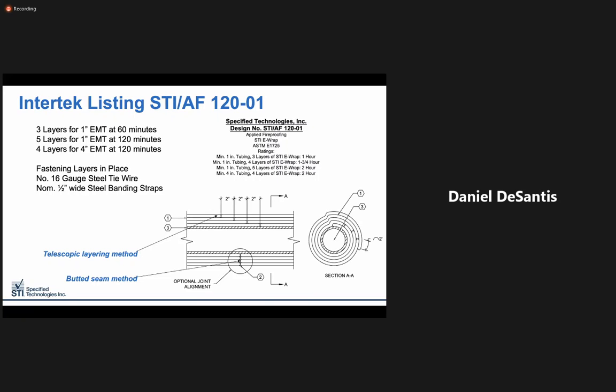When a butted seam method is used, a bead of LCI intumescent sealant is required on the outermost seam, where no additional sealant is required for the telescopic method. Either installation is completely acceptable as far as this listing is concerned. It's just a matter of installer preference.